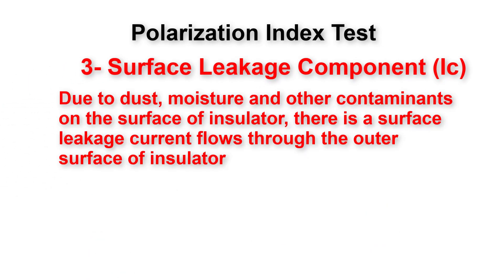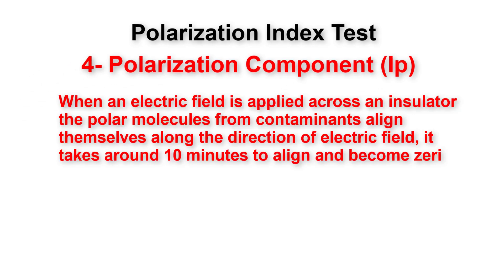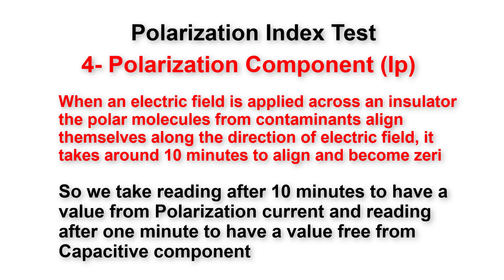Due to dust, moisture, and other contaminants on the surface of the insulator, there is a surface leakage current flowing through the outer surface. Finally, there is a polarization current: when an electric field is applied across the insulator, polar molecules from contaminants align themselves along the direction of the electric field. This alignment takes around 10 minutes to complete and then decays to zero — which is why we take the megger reading after 10 minutes, to ensure our result is free from polarization current.